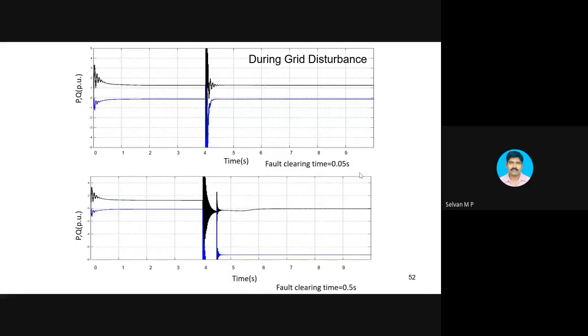So definitely within 0.5 second, see, this is 1 second, the fault will be cleared. But still, within that time period, as soon as the fault happens, the real power goes zero and the reactive power is enormously increasing. The black one is the real power, the blue one is the reactive power. Black is real, blue is reactive. Real power goes zero because in the meantime there is no magnetization, the speed increases and the machine cannot generate. Reactive power demand keeps on increasing. Even after clearing the fault, there is a reactive power demand because the machine speed is high and it is not able to supply any real power.